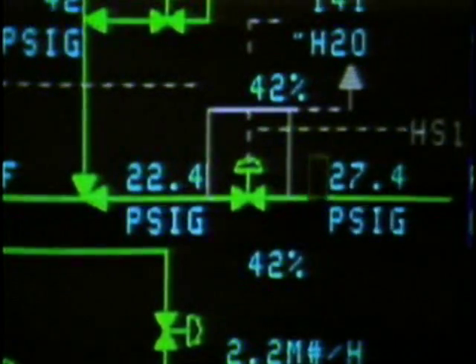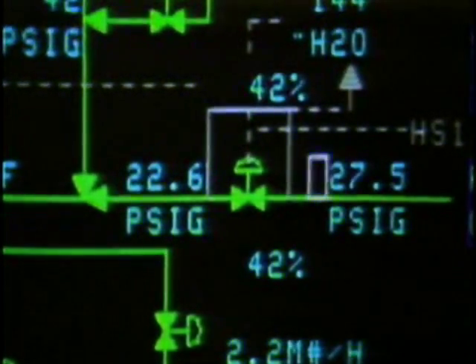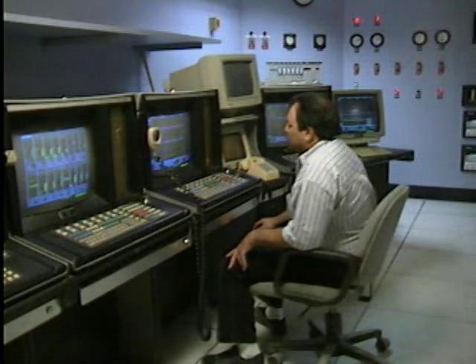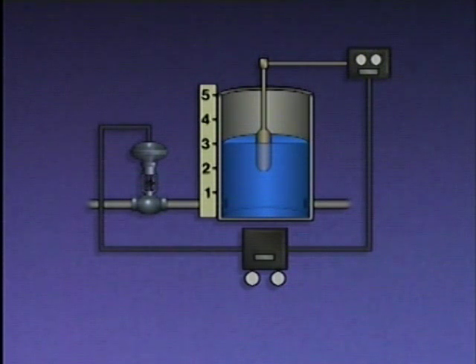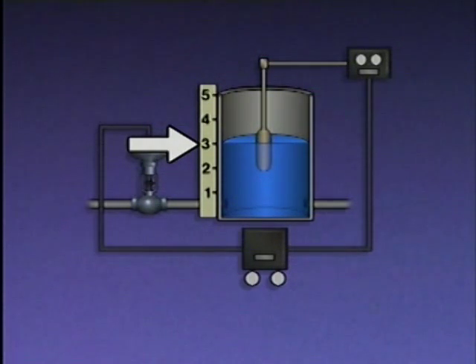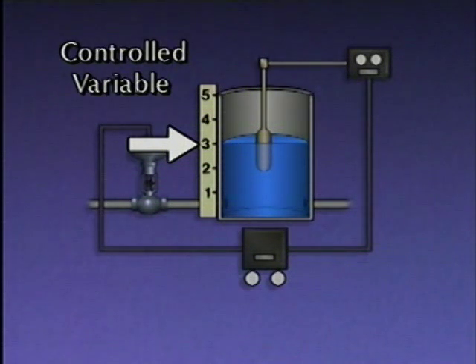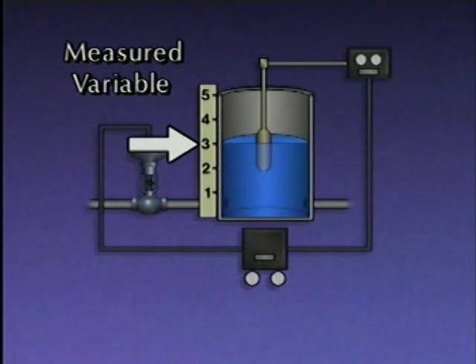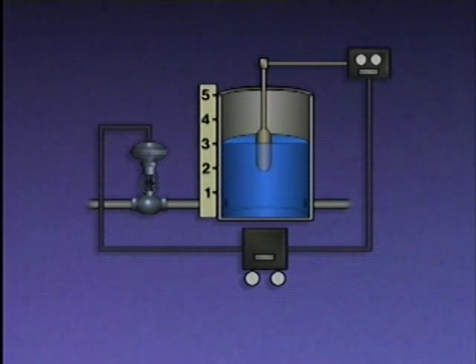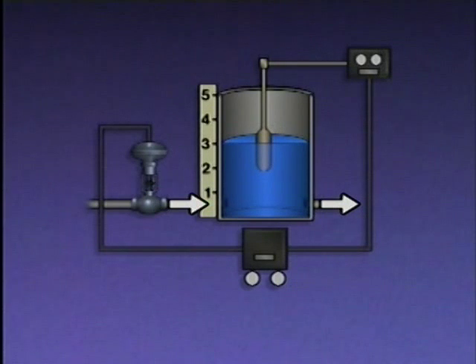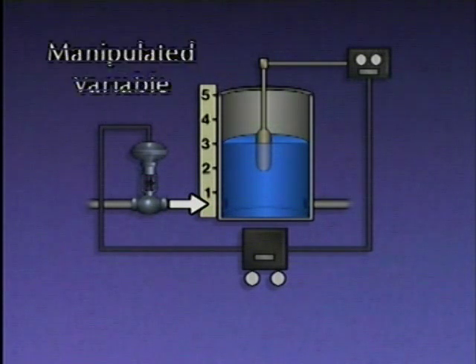Automatic control is basically a form of control that's performed with little or no human intervention. To get a better understanding of how an automatic control system works, we'll use this simplified illustration of a system that's used to control the level of water in a tank. Since the level of the water is what's maintained at a desired value, it can be thought of as the controlled variable in the system. It can also be thought of as the measured variable, because the control system uses it as a basis for making operating changes. The level of the water will remain constant as long as the flow of water into the tank equals the flow of water out of the tank. In this system, the water level is controlled by regulating the flow of water into the tank. For that reason, the flow of water into the tank is called the manipulated variable.